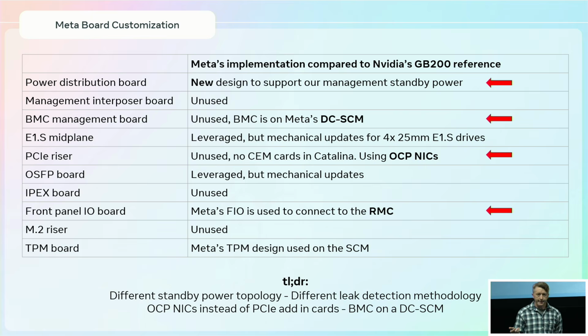The BMC is on the DCSCM. This is an OCP standard, a pluggable form factor with the BMC on it, and it provides our management. It looks at the fans, gives out-of-band access, sees the sensors, and handles all control of the rack. We've standardized on this and are using it throughout our hardware. So for us, we wanted to use a DCSCM.